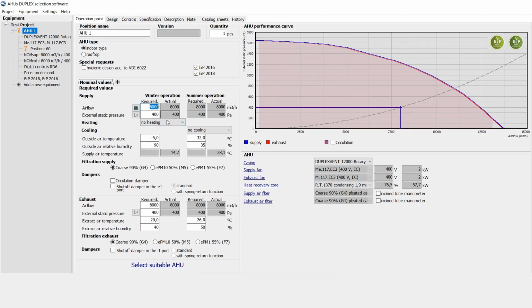Again, here we've got our air volumes and resistances. Let's put quite high resistances in for a thermal wheel, because thermal wheels can cope with higher external static pressures, since there's a lower pressure going across the wheel. So these units may give you better SFP, specific fan power, values than our plate heat exchanger models, for example.